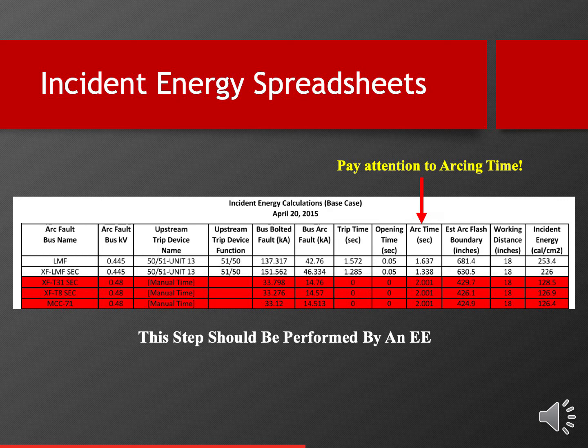So pay attention to the spreadsheet, especially the arcing time column, and be aware of anything that's at 2 seconds means it timed out. It didn't trip out, it burned in the clear. And that would mean that the labels are understated, is what it basically means. And of course, this step should be performed by a double E. Let's go to the next slide.